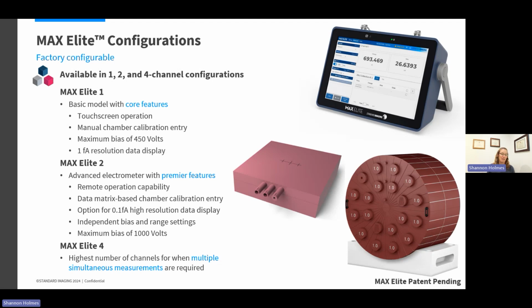And the other place that it's very frequently used, where people use more than 2 channels at a time, would be the tomotherapy cheese phantom, or a similar phantom where you might have chambers in multiple locations within a larger QA phantom, and you want to irradiate them all with a single irradiation.